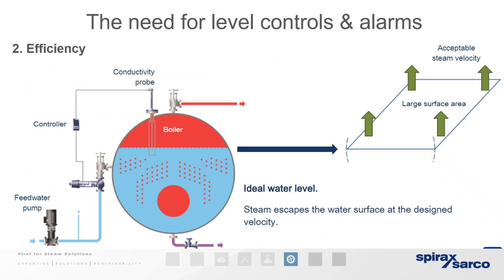Again here, the reason you need accurate control is also for efficiency. As you can see, the area of the water where it's flashing off is here, so your steam is being produced here. By being at this point in the circle, you have a larger area, so you're releasing more steam. It's the ideal position for this heat release to happen. Modern boilers are smaller than, say, 50 years ago, so they hold less water and therefore they need to respond to demand quickly.